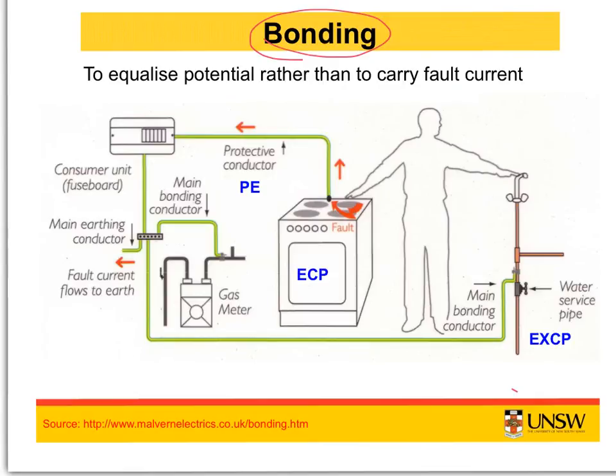So what we have here is something called an ECP. What is ECP? It's the external conducting part, or you can define this as the external part of an electrical equipment which is made of a metal, therefore it's capable of conducting electricity, but usually it is earthed or it's functionally not connected to the equipment as such. And then we have PE, which is the protective conductor. The protective conductor is the earth wire which takes the ECP to the grounding point. And then we also have EXCP, which is the extraneous conducting part. Extraneous conducting parts are any conducting metals.